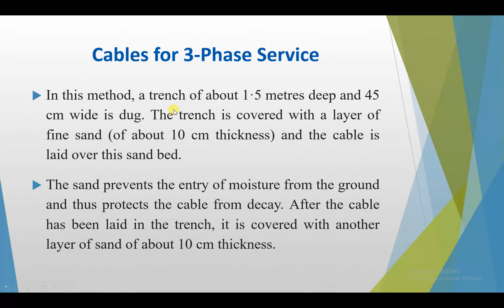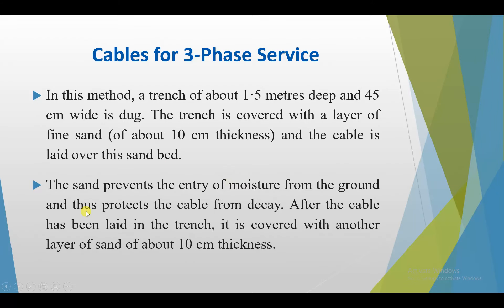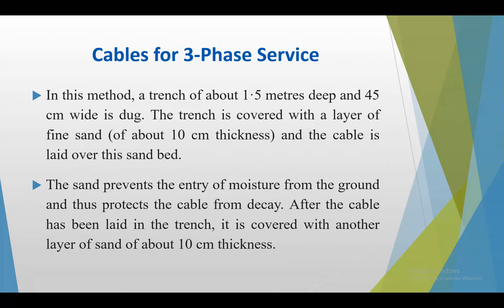In the direct laying method, a trench of about 1.5 meters deep and 45 cm wide is dug. The trench is covered with a layer of fine sand about 10 cm thick, and the cable is laid over this sand bed. The sand prevents ingress of moisture from the ground and thus protects the cable from decay. After the cable is laid, it is covered with another layer of sand about 10 cm thick.